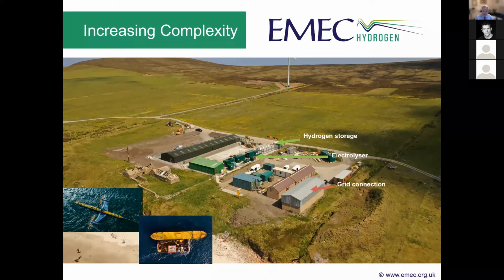The original grid connection is a 33 kV grid connection that links straight into the Orkney main, run by SSE, and then that hops across into our original substation that was built in about 2006, stepping down to 11 kV at that point. We have a 900 kilowatt community wind turbine that also now links into our site, and we have cables running up the beach from the tidal turbines.